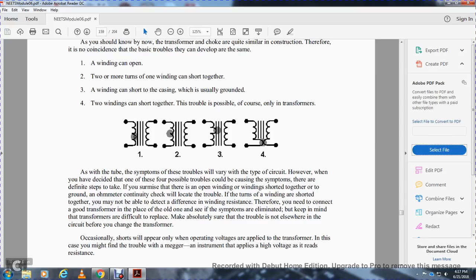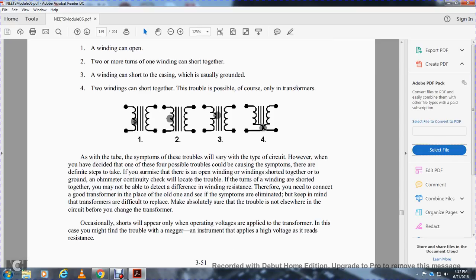Keep in mind that the transformer is difficult to replace, but make absolutely sure the trouble is not elsewhere in the circuit before you change the transformer. Occasional shorts appear only with the operating voltage applied to the transformer. In this case, you will find the trouble with the megger instrument, applying the high voltage as it reads resistance.